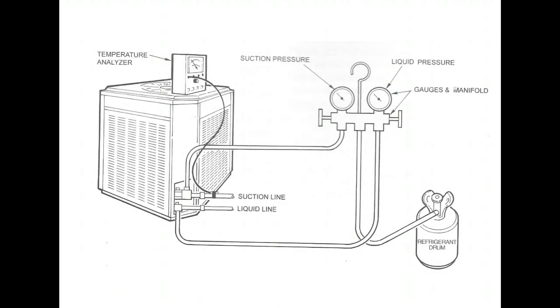Okay, so here is our system once again. It's all set up, ready to go. So what you'll do is you will back off the low side valve on the manifold gauges counterclockwise. That will allow that refrigerant to come through, and then you'll charge your system step by step, slowly. Don't overcharge it and allow the system to stabilize between each dose of refrigerant.